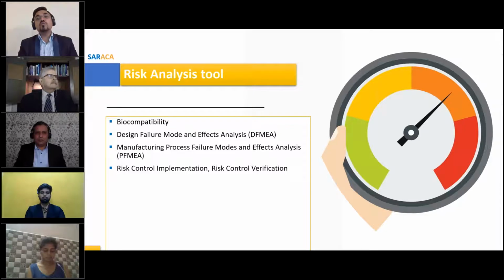Then you can move forward to the design phase. In this design phase, as Kuldeep told you in the earlier slide, DFMEA is a very necessary tool to do risk analysis, and this is a very tedious job for all companies. So during the design phase, you need to do a very detailed DFMEA, that is design failure mode effect analysis, so that the design of the device is low risk, and once the device has been manufactured, the overall residual risk will be acceptable.